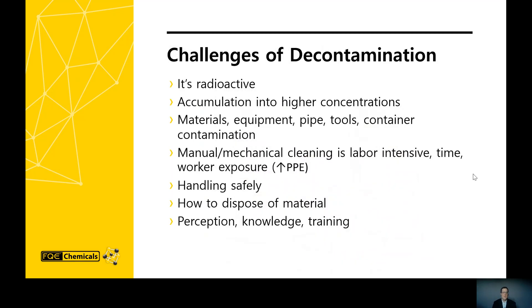The challenge of decontamination is that it's radioactive, and once disturbed, the chance to pick it up or put it into the air is increased. We accumulate this radioactive material into higher concentrations, and all material used during decontamination — the pipe, tools, and containers — are all considered contaminated and will have to go through a decon process. Mechanical or manual cleaning is labor-intensive, takes time, and increases worker exposure, thus requiring higher levels of PPE. The mineral scale associated with this, such as barium sulfate, is so hard it's measured on the Mohs hardness scale like a diamond, making it difficult to break apart, and even knowing how to dispose of the material may be a problem.